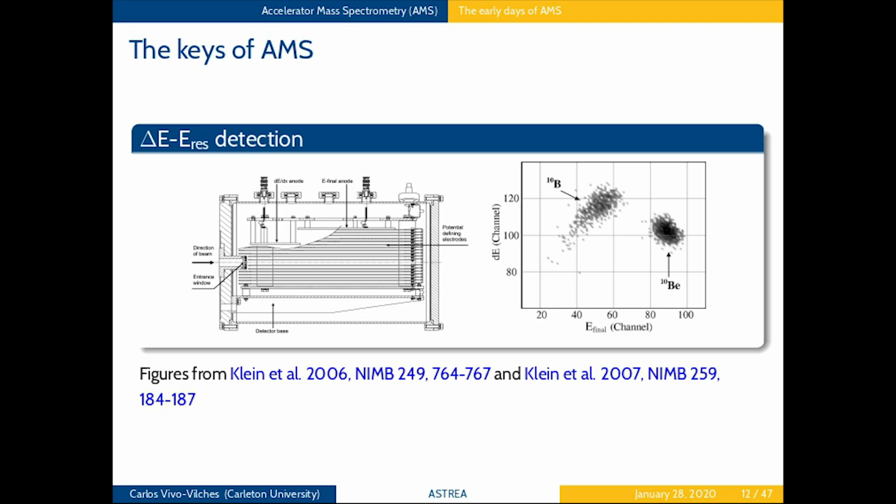Also, in these gas ionization chambers, you can separate the anode, for example, into 2 or several anodes. Here we can see an example in the bibliography of how different ions ionize the medium. Here we have, for this case, the energy deposited in the first anode and the energy deposited in the second anode by different ions.